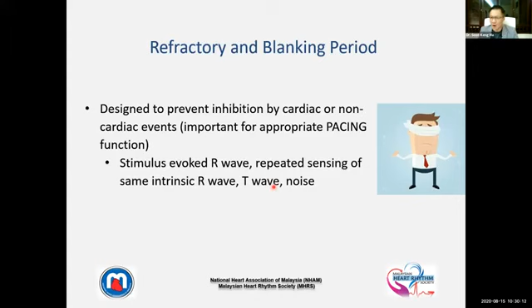Why T wave? Let me illustrate for you. Now look at this rhythm strip here. You have got a ventricular pacing spike with a capture, a QRS complex. There will be a blanking period in the beginning because the amplifiers have been saturated. You need to switch off for that short period of time, blank it, let it go blind for a short period of time. And followed by a ventricular refractory period, meaning that now I open my eyes, I see, but I don't react. Just now, I don't want to see. I don't see, don't react, just now in blanking. Now I see, but I don't react. But I jot it down. I record for my implant, for my physician to see, for the implanters. So ventricular refractory period is a period of time in which sensed events are ignored for timing purposes, but are included in diagnostic counters. So you still can see them in the diagnostic counters.